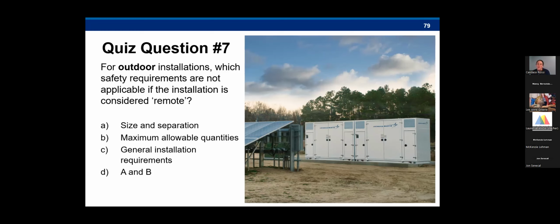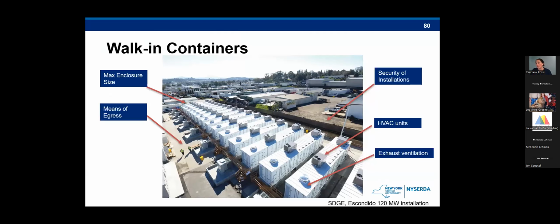All right, I'm seeing an abundance of D's, which is correct. Both size and separation and max allowable quantities are not required for remote outdoor installations. So here is just an example of some larger walk-in containers or cabinet systems. You can see there's the maximum allowable, the maximum enclosure size. It's also important to note that the HVAC units and exhaust ventilation is not included in the maximum enclosure size. So that's why those are not included as being above there.